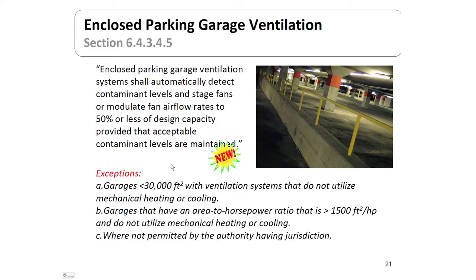This is a new requirement for enclosed parking garage ventilation systems. The system has to detect contaminant levels in the garage and then stage the fans or modulate the fan airflow rate to 50% or less of design capacity, provided the acceptable contaminant level is maintained. That is the number one requirement since it affects health and life safety. Exceptions include garages less than 30,000 square feet that do not use mechanical heating or cooling, garages with an area-to-horsepower ratio greater than 1,500 square feet per horsepower that also do not use mechanical heating or cooling, and locations where the local authority does not allow it.